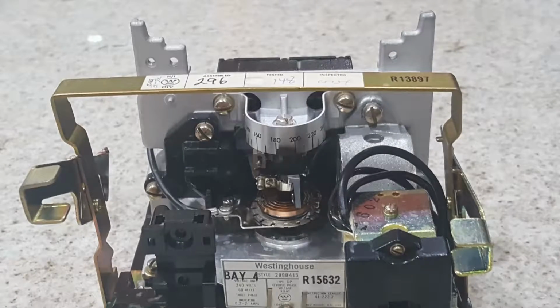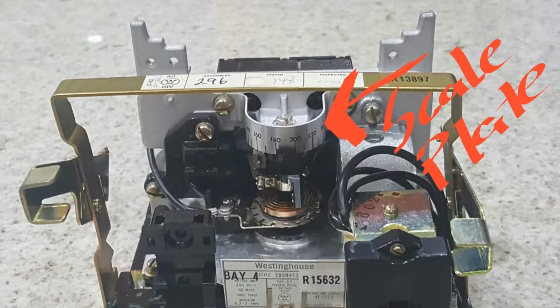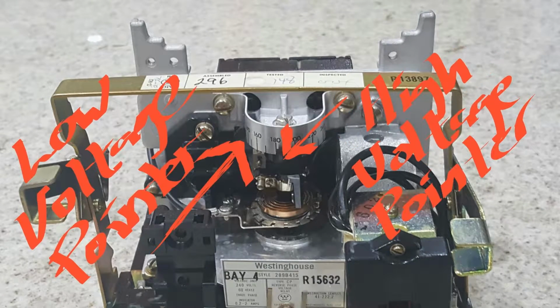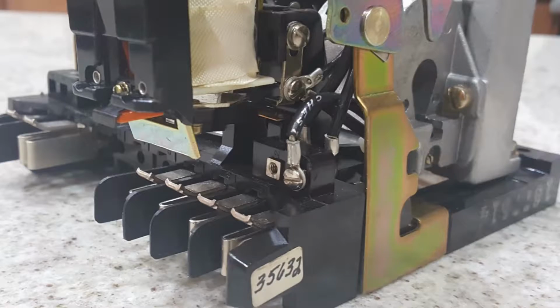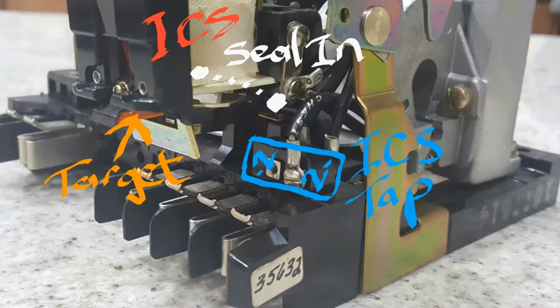We're going to take a look at the scale plate. That's going to determine where we place our 27 low voltage and our 59 high voltage pointers, which have contacts on the bottom of them. Here's a view of our ICS, or indicating contactor switch. It's set up on our low voltage side. You can see the tap points, the seal-in, and the target at the bottom.